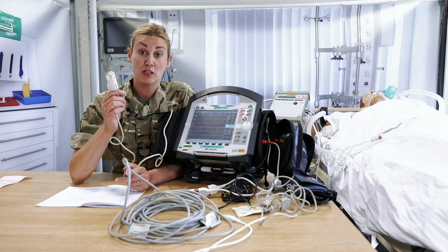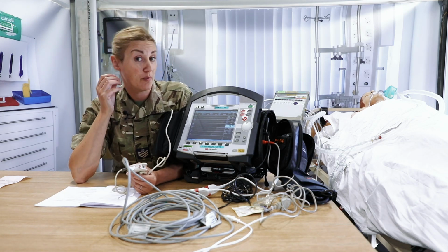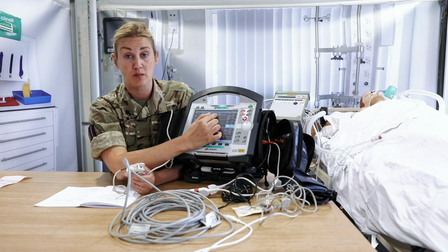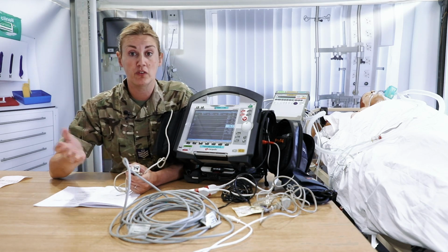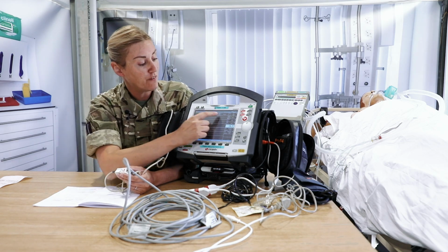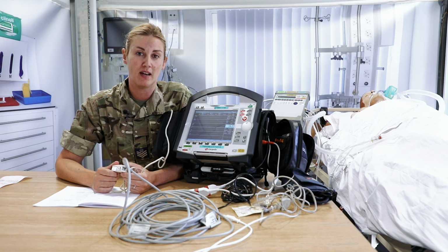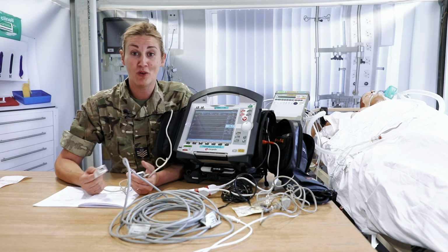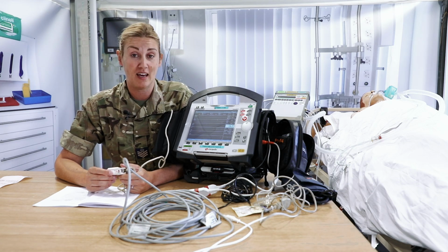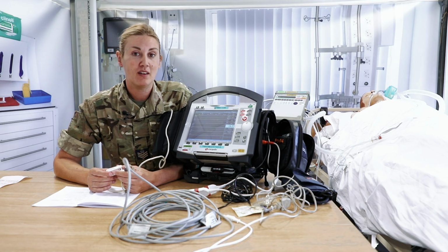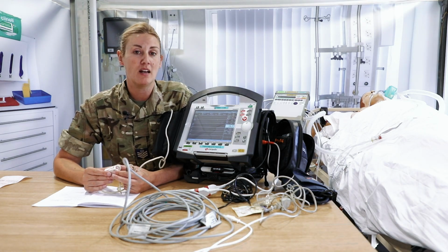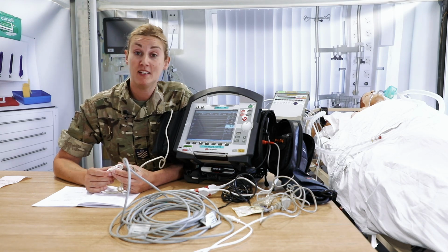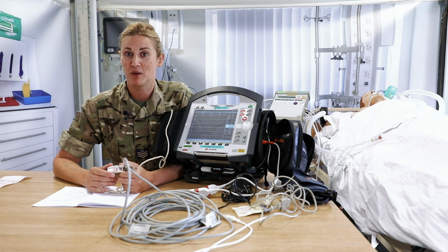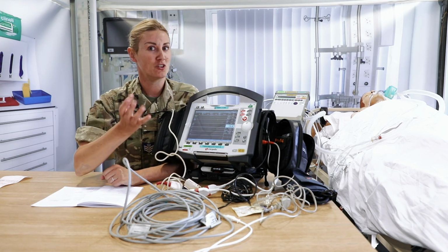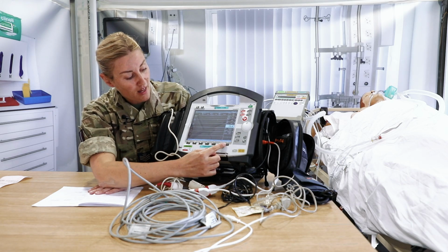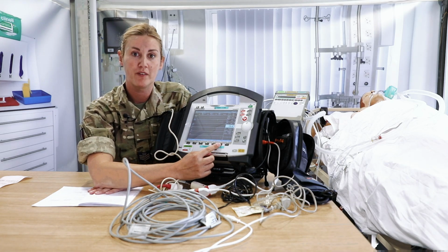Finally, we're going to check that the SATS probe works. Obviously connect it to your finger, use the ear probe, connect it to an ear, and just confirm that you get some readouts on our SpO2, our pleth pulse, so a reading of a pulse from a SATS probe, and a function here called PI, which is perfusion index. So this is a function that Corpuls sold Defence, saying it would be very useful for us to indicate patients' perfusion peripherally. Most of us don't use it. It will give you a number. Lower numbers indicate poor perfusion, higher numbers indicate good perfusion, but we don't really use it. So just check for a number. And that is all the leads that we're going to check when we press that non-invasive blood pressure button.